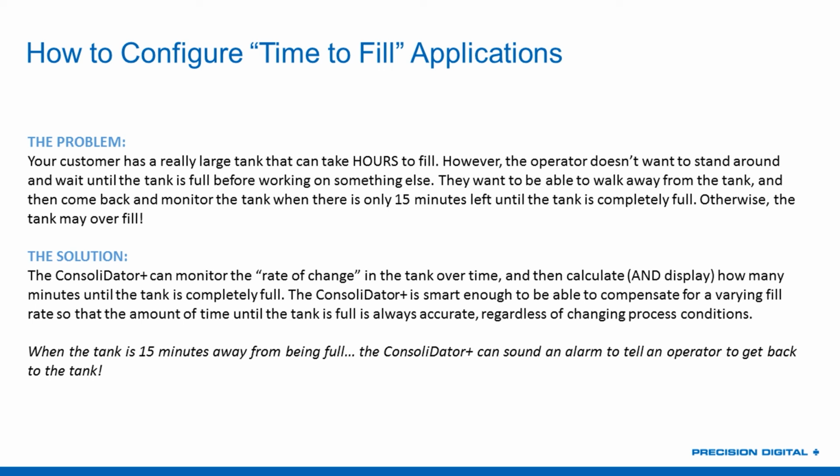Well, with a consolidator, we do some clever math. We use our rate of change channel, and we are able to display how long it's going to take until the tank is at full capacity. And that's going to be dependent on the tank fill rate and the amount of volume, the amount of material we have in the tank. So those two conditions are changing over time, yet the Consolidator Plus can still provide you with an accurate readout of how long it's going to take.